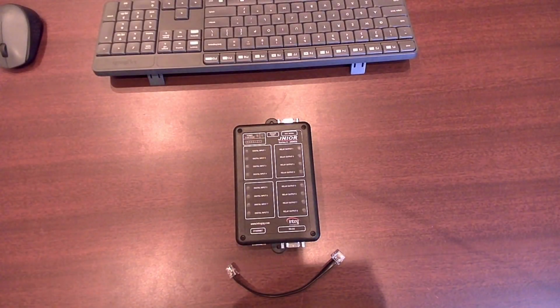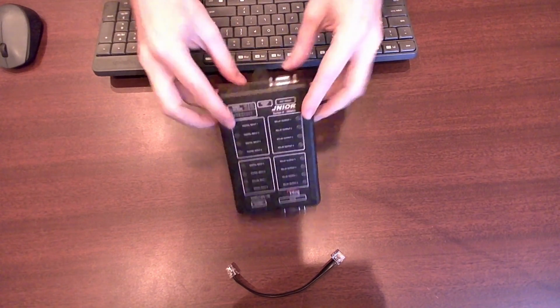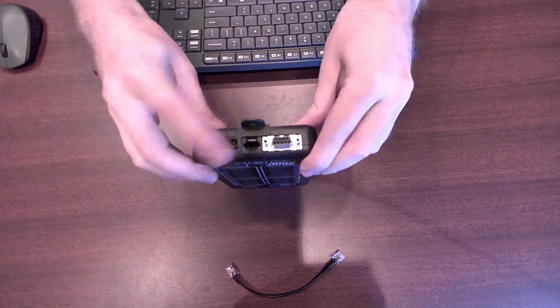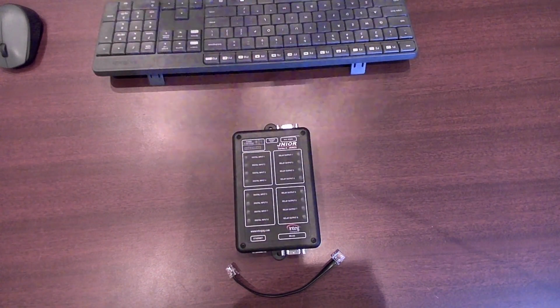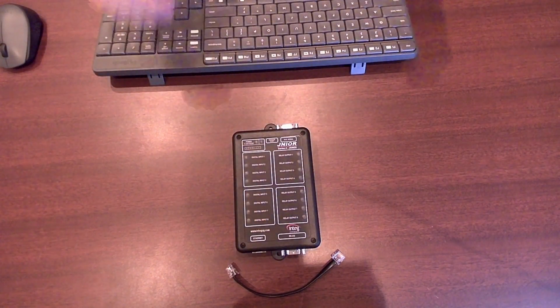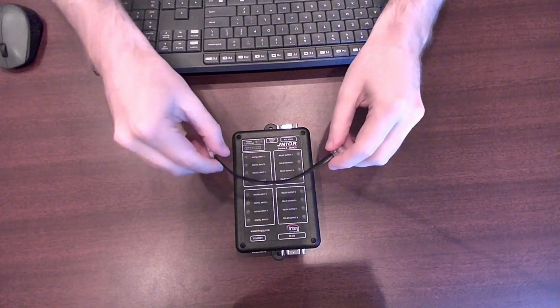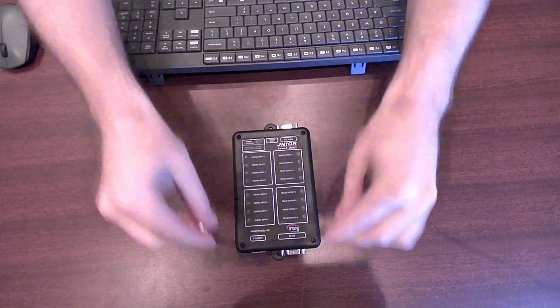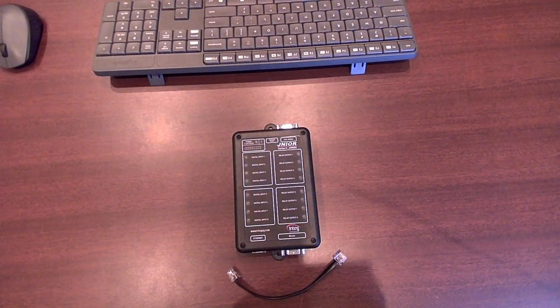Expansion modules can be used with both the Series 3 and the Series 4 Junior. Currently, INTEG offers several different types of expansion modules to use. All expansion modules connect via the sensor port, located at the top middle edge of the Junior, right here. The cable that connects expansion modules to the Junior is a 6-pin modular flat cable with RJ12 connectors. Each expansion module comes with a cable at a preset length, but if you're interested in making your own custom cable, there's a post on our website on how to do so.